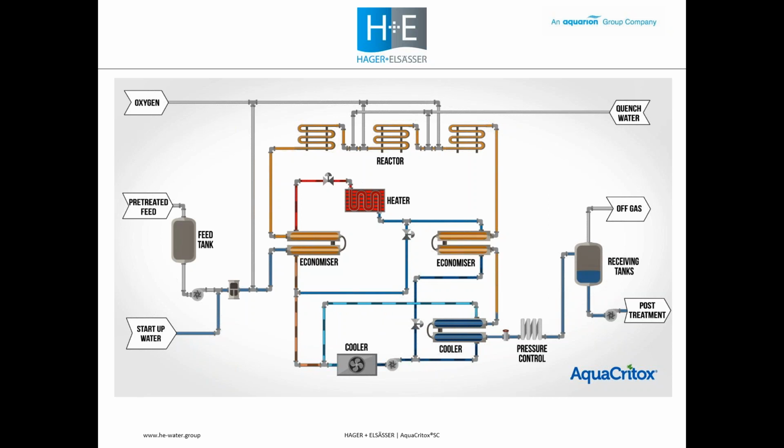You can see now that the heat transfer system is working. The water is circulating. We are cooling water using an air cooler rather than the water cooler. Heat from the hot process is exiting the reactor, and it's recovering the heat and allowing the heat transfer to transfer heat from the back end of the process to the front end of the process. The electric heater will run to maintain a temperature of 250 degrees C.